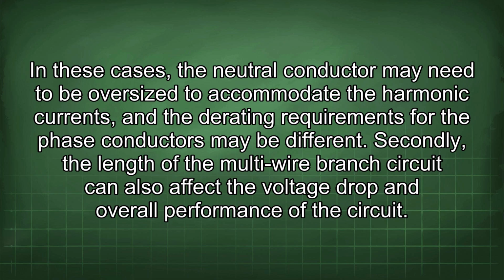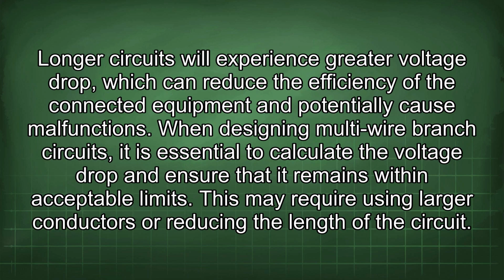Secondly, the length of the multi-wire branch circuit can also affect the voltage drop and overall performance of the circuit. Longer circuits will experience greater voltage drop, which can reduce the efficiency of the connected equipment and potentially cause malfunctions. When designing multi-wire branch circuits, it is essential to calculate the voltage drop and ensure that it remains within acceptable limits.